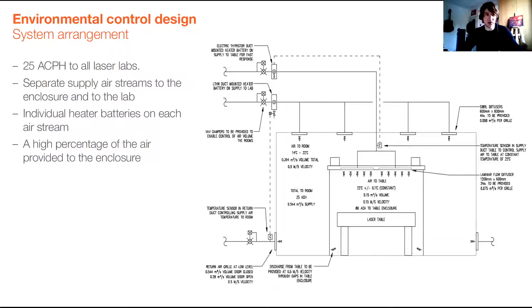So we had two separate branches from the ventilation system going to each lab, one going to the enclosure, and that would just be a constant temperature, and then one going to the room that would be a varying temperature depending on what's going on in the room at the time. So because this was quite new, that we hadn't designed this type of system before and weren't aware of many buildings that were achieving plus or minus 0.1, the project took the decision to build a mock-up to test the design solution before we built it on site.